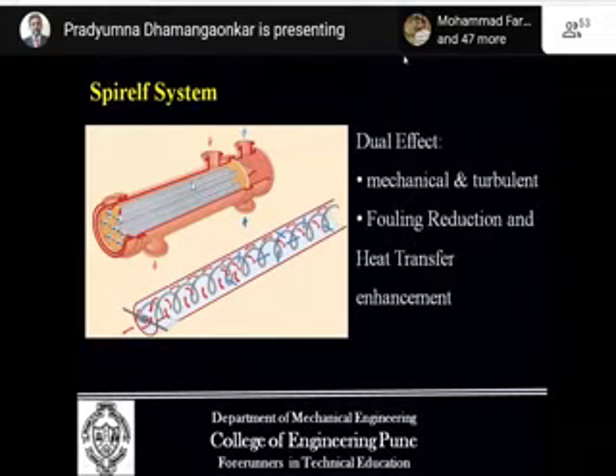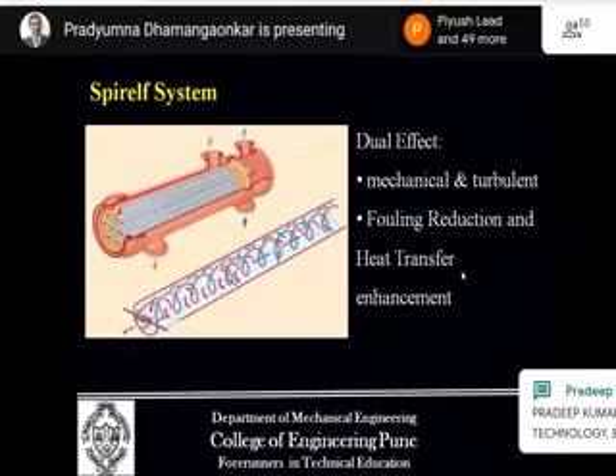It has a dual effect. One is mechanical and the second is turbulent. The mechanical effect leads to fouling reduction because there is no blockage, there is no space or surface which will restrict the flow, and thus the fouling is reduced. And second is the turbulent effect. Due to this, the heat transfer coefficient is increased because the turbulence is increased.